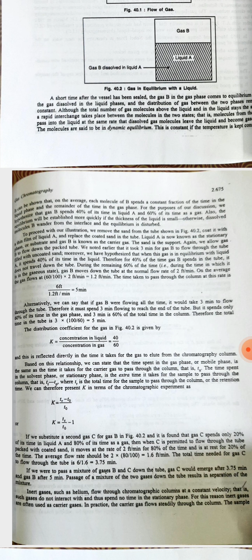So the distribution coefficient K that you will calculate is the concentration in the liquid upon the concentration in the gas, and this is reflected directly in the time it takes for the gas to elute from the chromatographic column. Based on the relationship, we can state that the time spent in the gas phase or mobile phase is the same as the time it takes for the carrier gas to pass through the column.